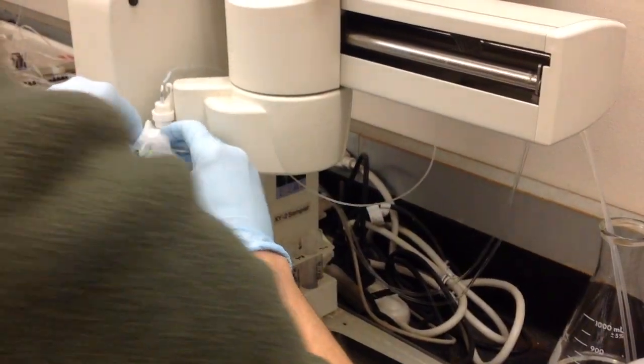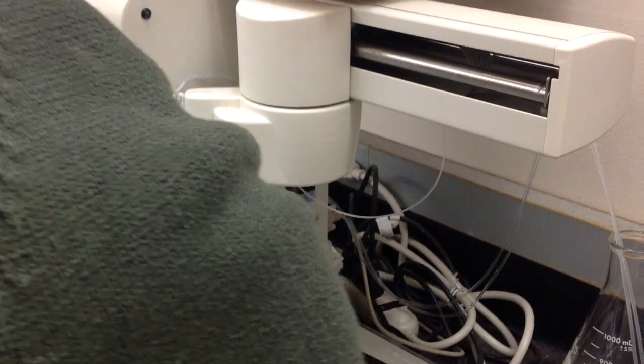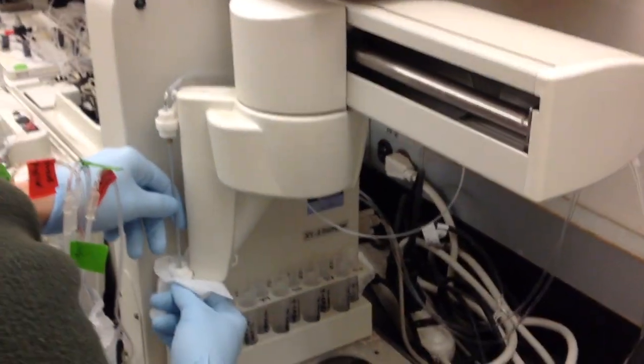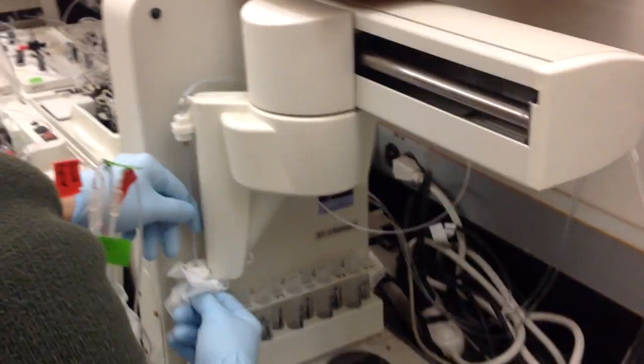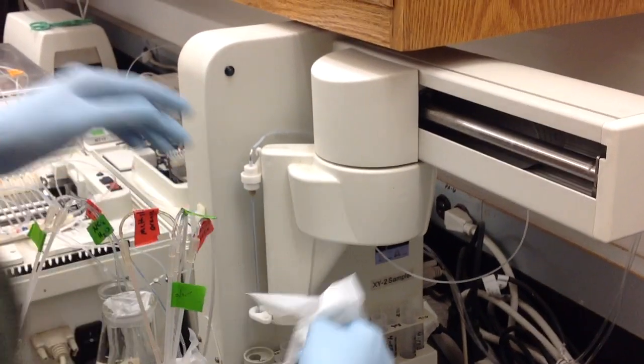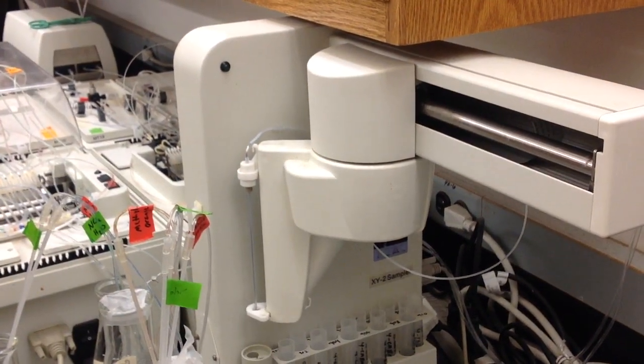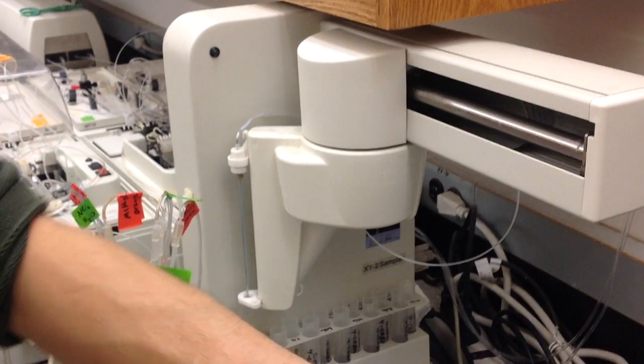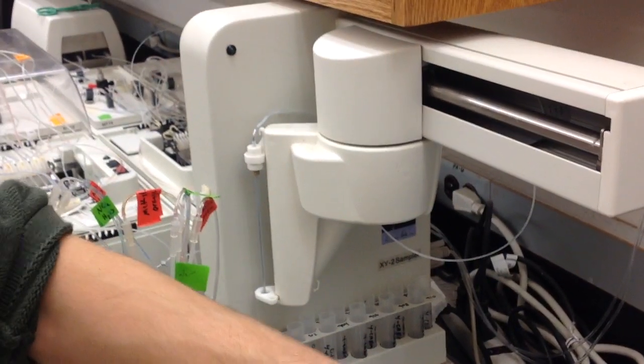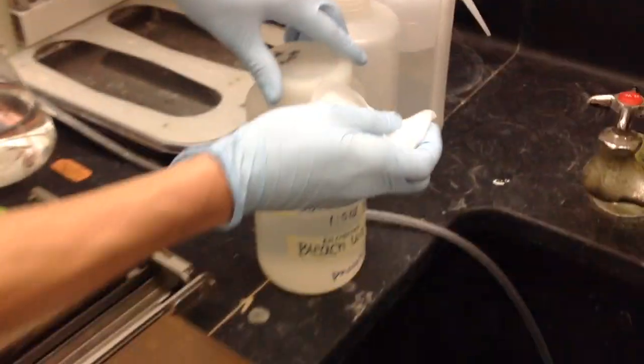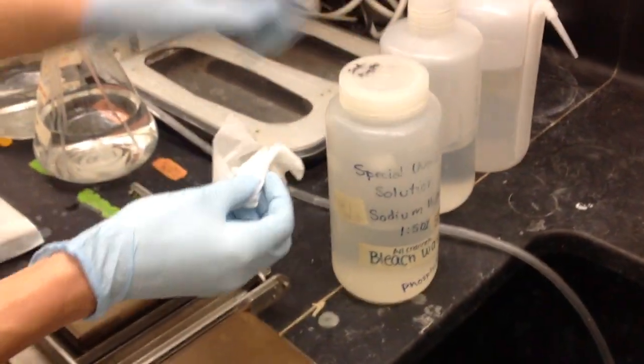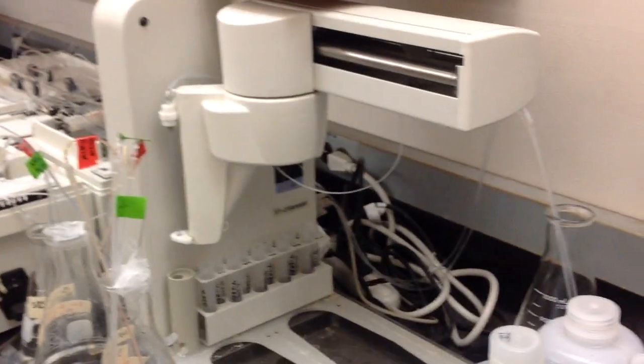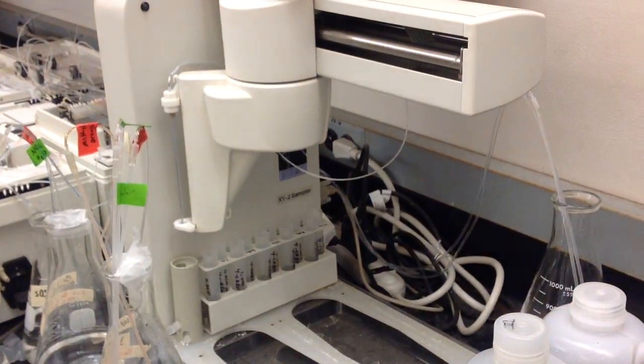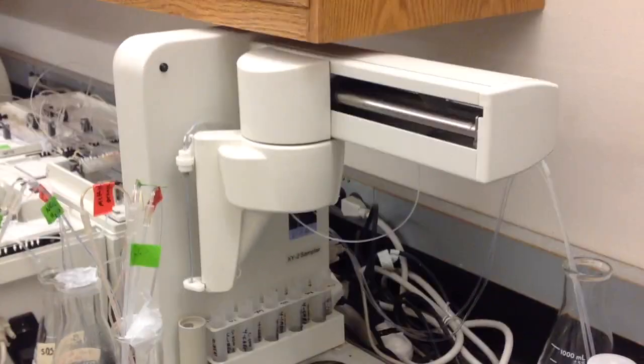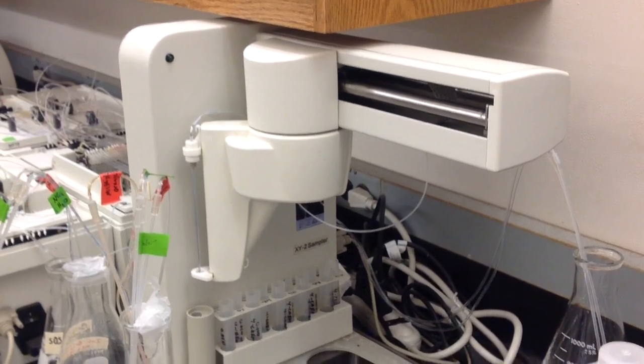How do you know when it requires some cleaning? Like I said, if you have really consistent baseline drift problems, that might be a potential troubleshoot. Unstable baseline drift. That's one of the things you can check: is the wash pot or the probe dirty?